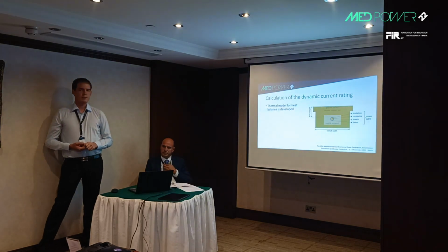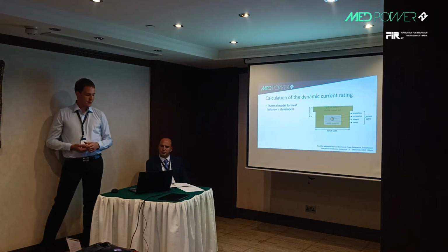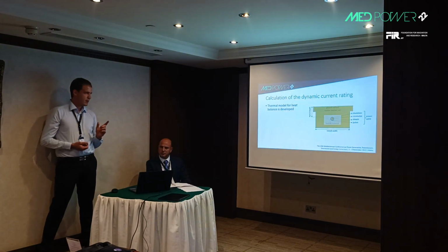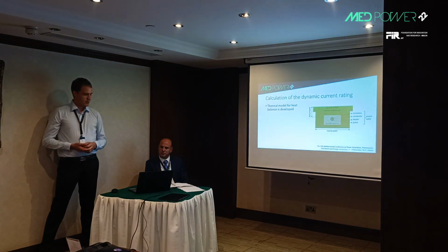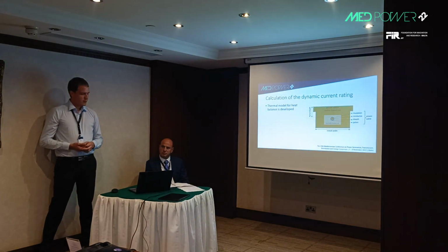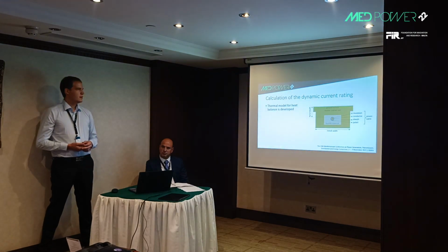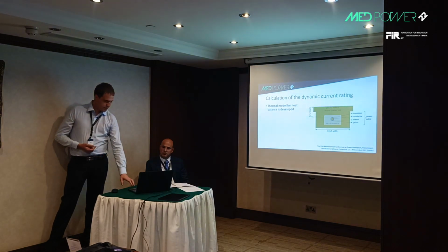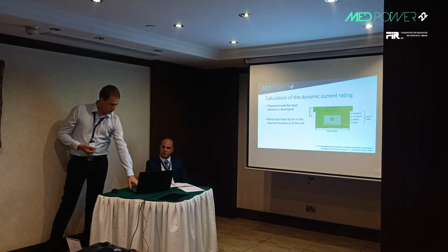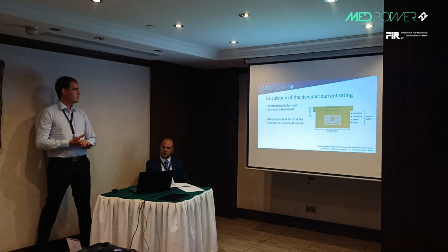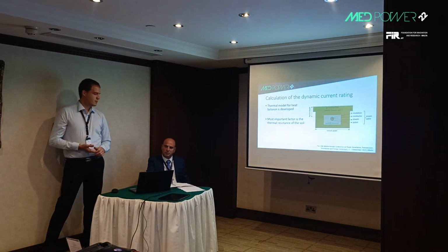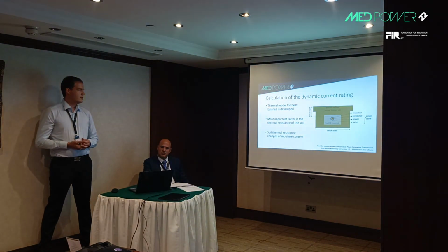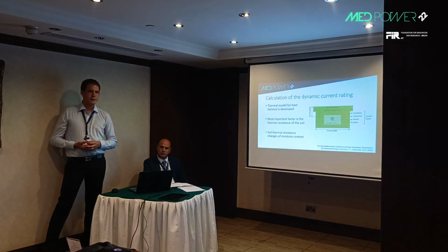We need a temperature distribution in the cable, and the soil thermal resistance between the power cable and the ground surface. And also the layout for the cable is important. The ground as well.